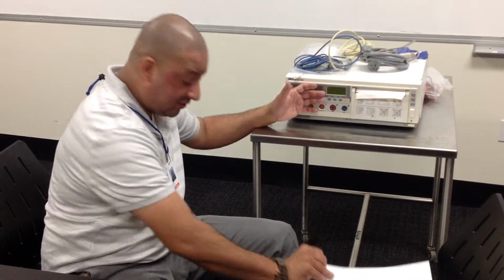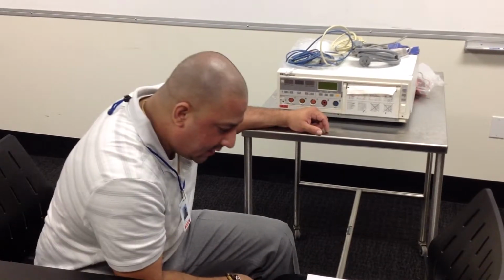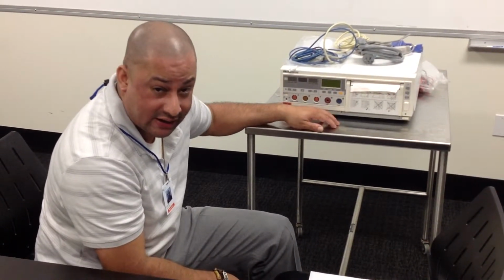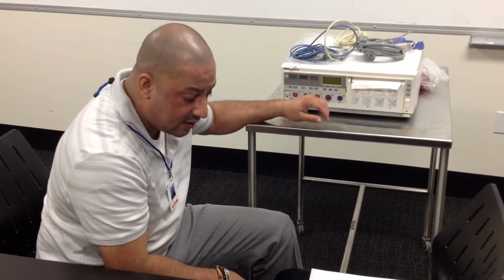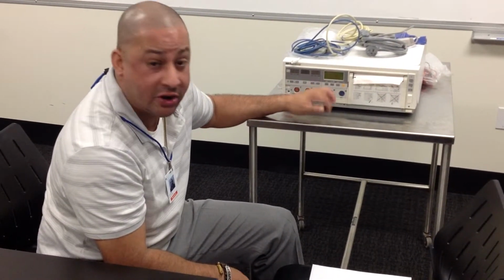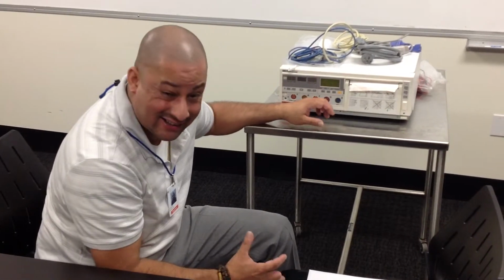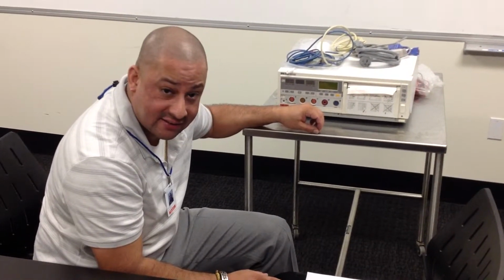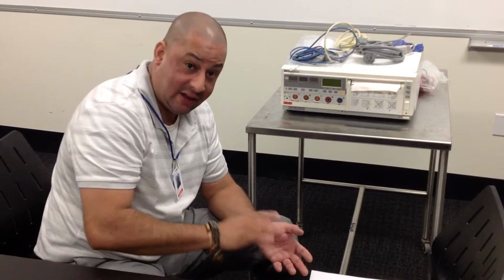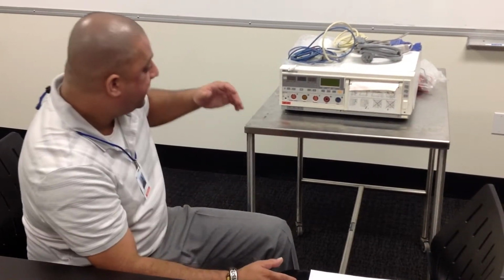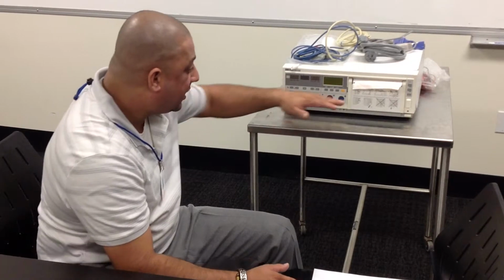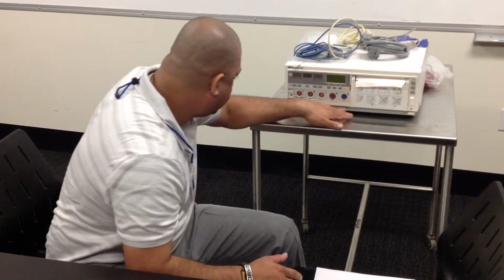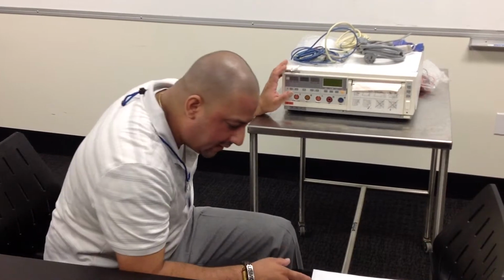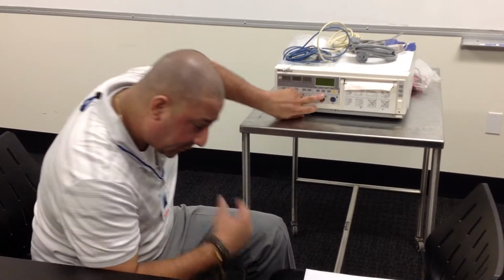And then you have to apply pressure to it. Now, this is the key. You have to apply exactly 220 mmHg, Hg being mercury, of pressure for 10 seconds specifically. After 10 seconds, the measurement should stabilize itself. Okay? Once you do that, the last thing you do is press another button that says store calibration. I don't see it here either, so we'll assume it's here. Just hit the store calibration button. And then in the display, you'll see the new value and the previous value. So that's how you calibrate that.